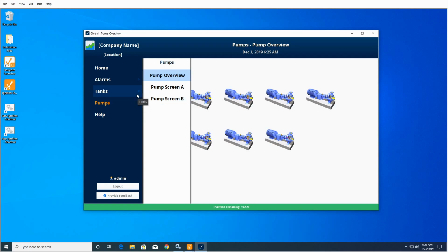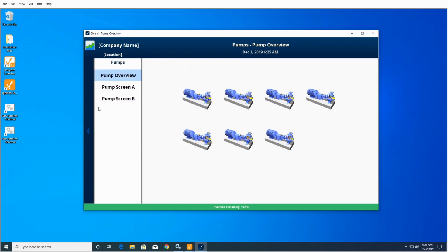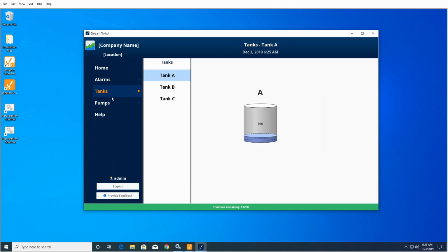At one location there's 50 people using Ignition at any time, so that's 50 people that would be making alarm requests if I had done it in the client. So I have that moved to the gateway. It doesn't update as fast, but it's good enough for showing where the problems are.